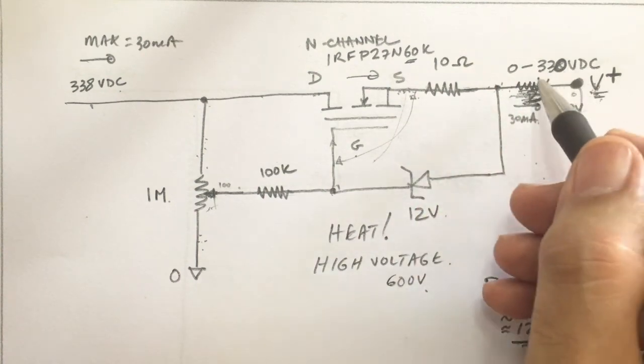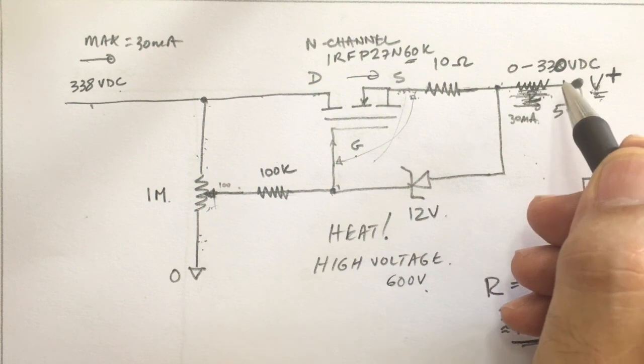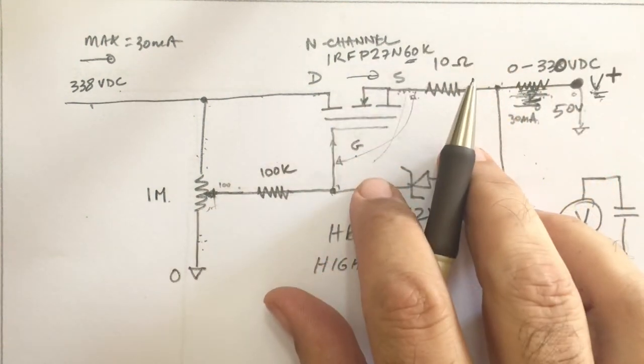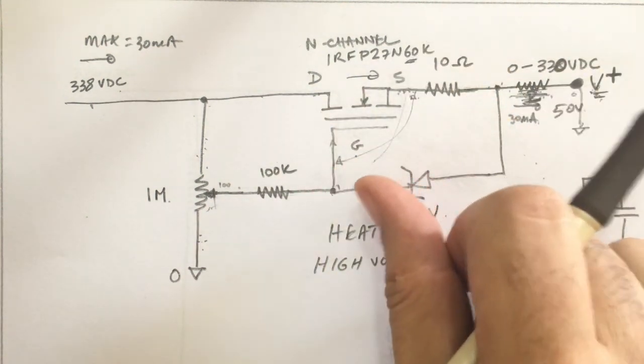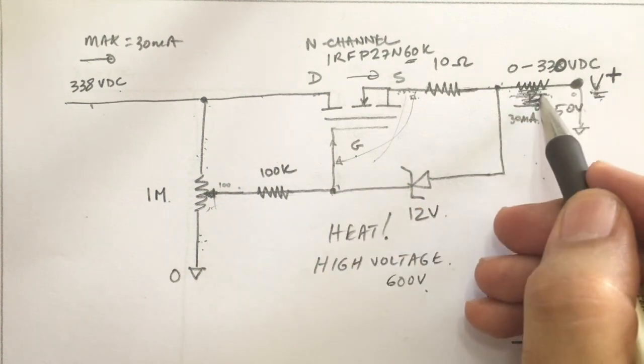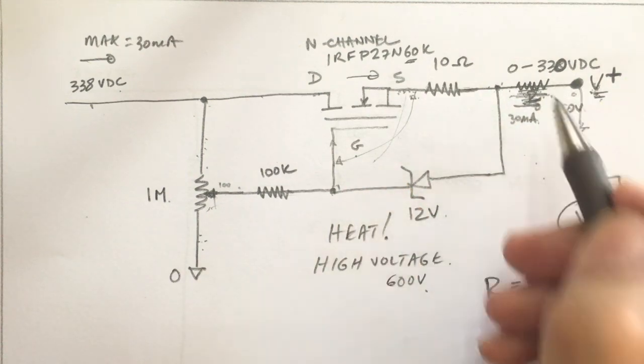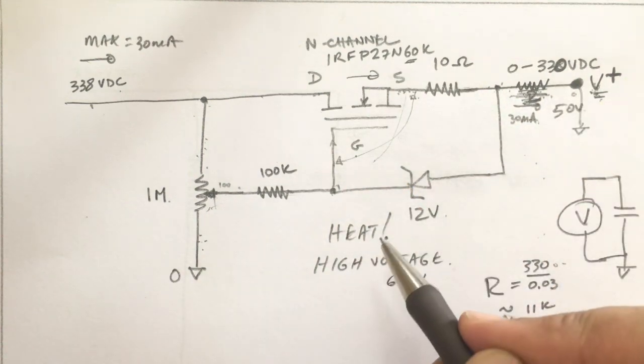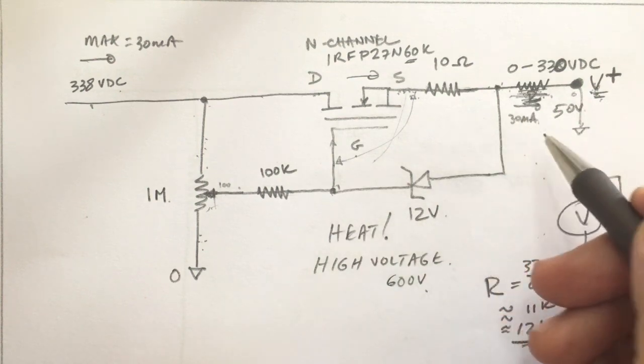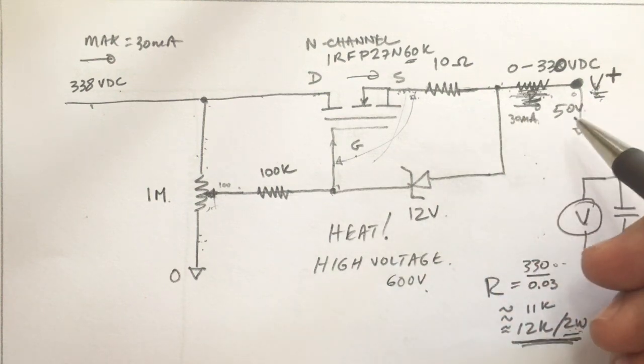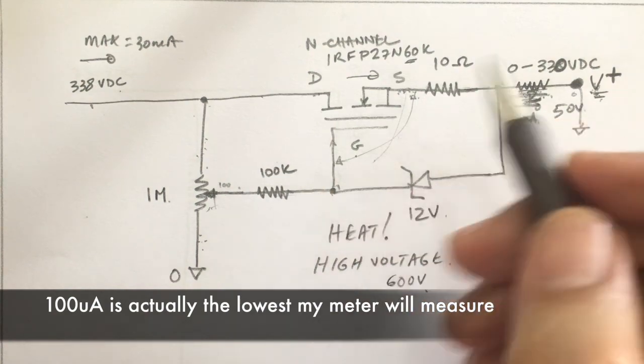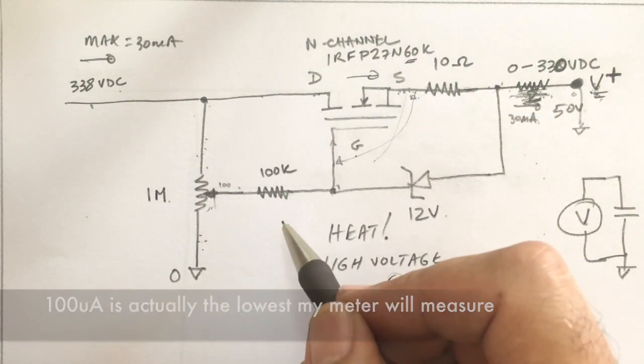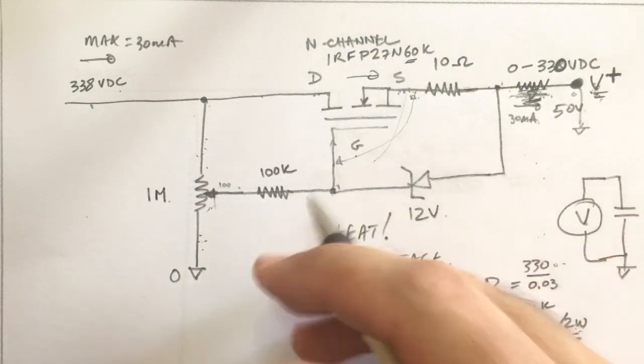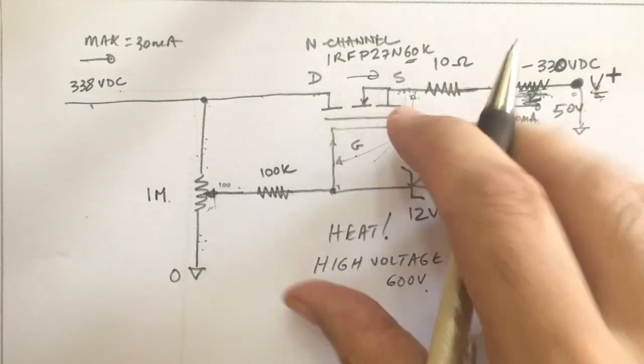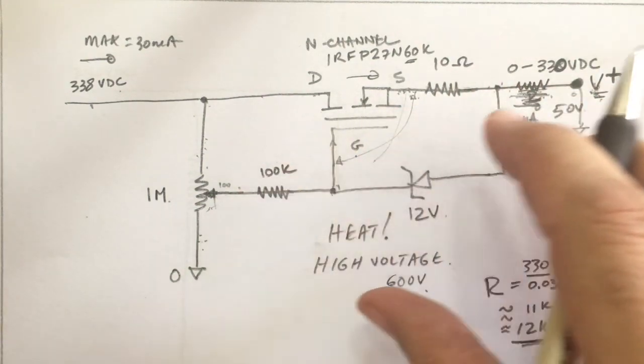If you have an ammeter that measures up to 100 microamps, like the one I have, I need to make sure I can read 30 milliamps, 10 milliamps, 1 milliamp, and also up to 100 microamps. I'd like to be reading somewhere around 1 or 2 microamps every time I put a capacitor in here - that's utopia, meaning my caps aren't really leaking - but it's not going to happen.